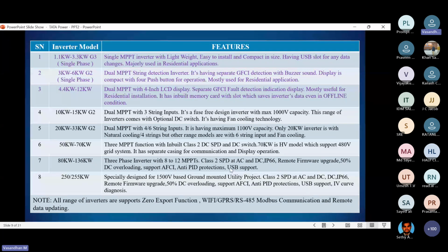USB support is also common. And 255, 255. This is the maximum range nowadays used for utility ground mounted projects. So this is a 1500 volt based ground mounted project. We can use this inverter with class 2 SPD, AC and DC side both, class 2 SPD, IP66 protection always there. Remote firmware upgrade, 50% DC overloading support, AFCI fault, anti-PID protection, as it is normal, same in other inverters also.